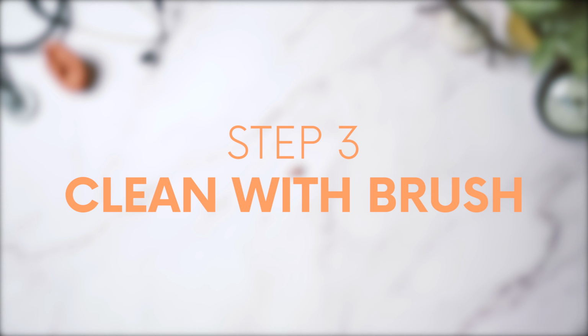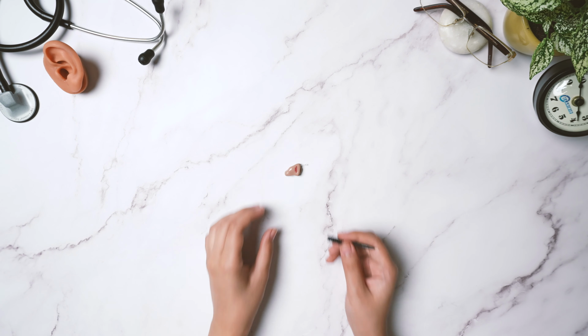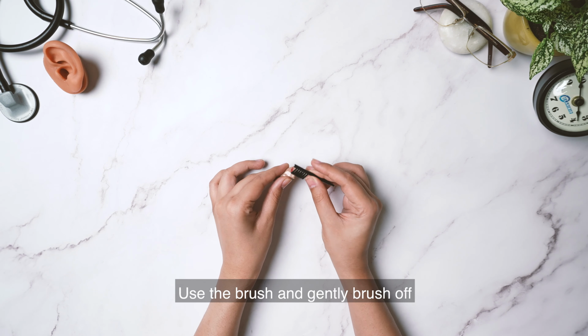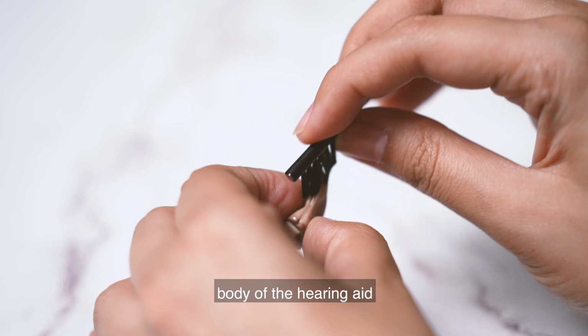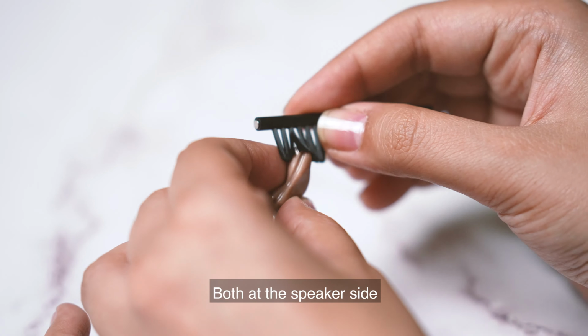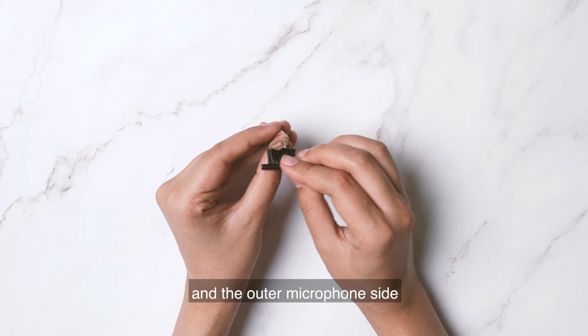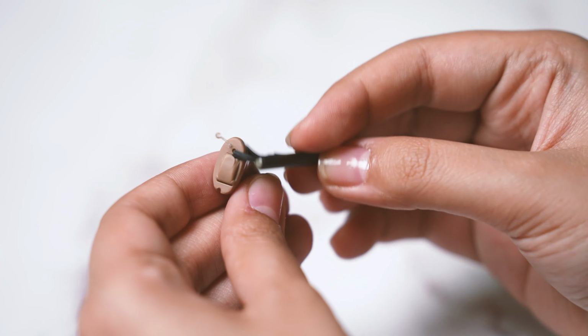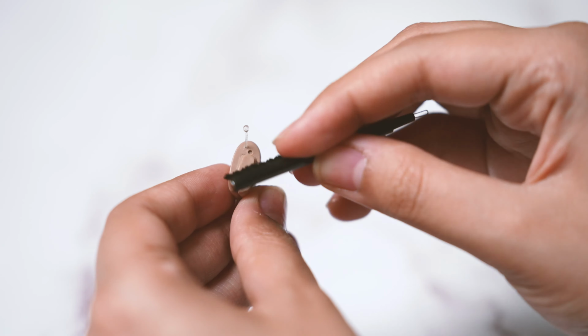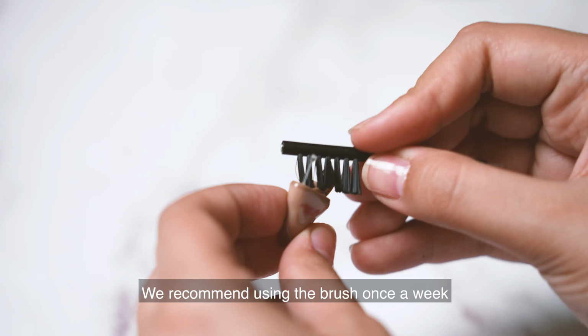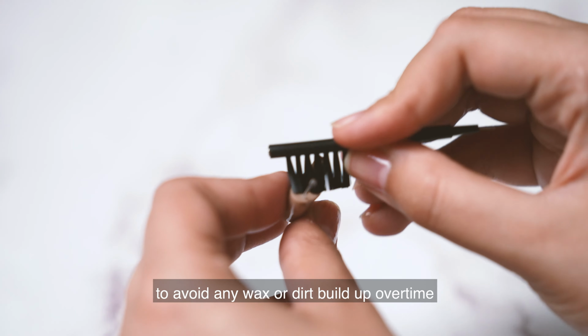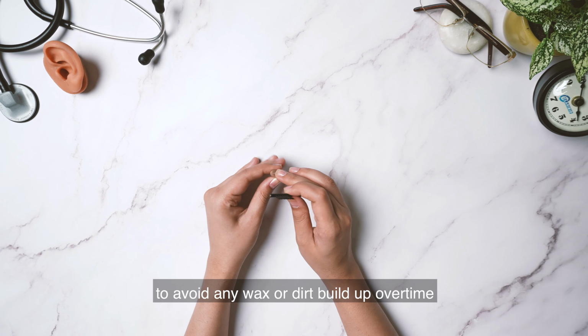Step 3. Use the brush and gently brush off any remaining dust from the body of the hearing aid, both at the speaker side and the outer microphone side. We recommend using the brush once a week to avoid any wax or dirt buildup over time.